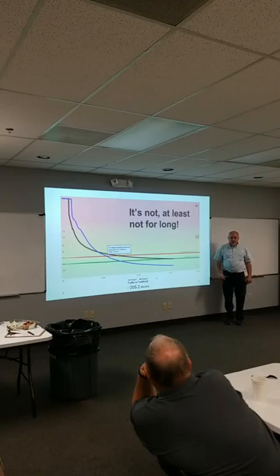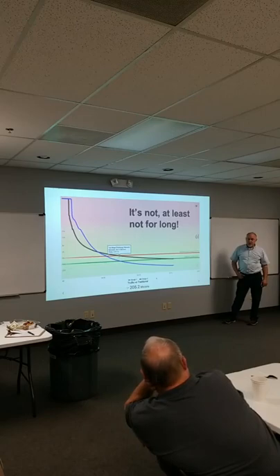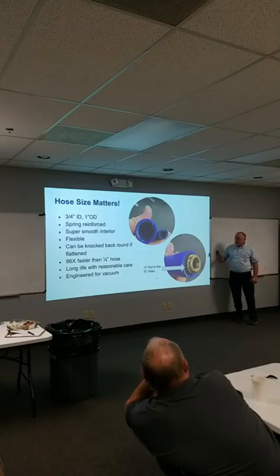At 7 minutes I'm at 500 microns versus 15 minutes on the same tank, right? And who would think that if you just bought a 12 CFM pump, hooked it up, paid all this money, and hooked up the 1/4 inch hoses, I'd beat you? It'd be like racing a Ferrari versus a Yugo. And that's literally what it looks like on there. But if you hook a boat anchor to the Ferrari, or take off its wheels, it's just not gonna go that fast, right? So it's faster, but not for long. So the hose size really, really matters.